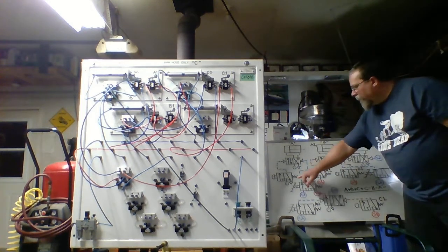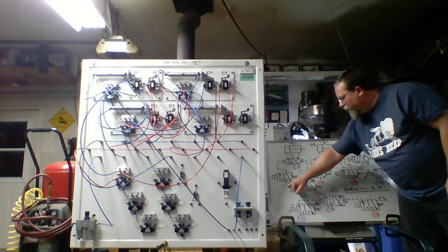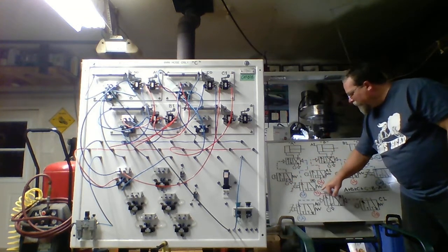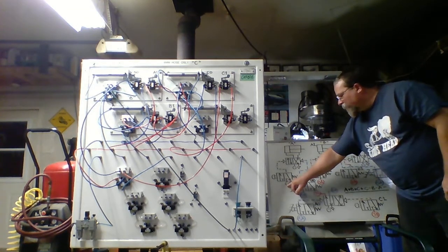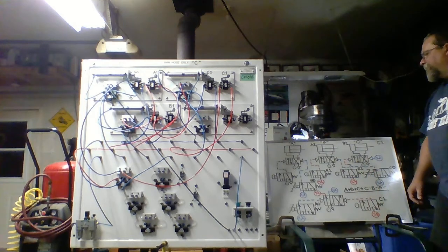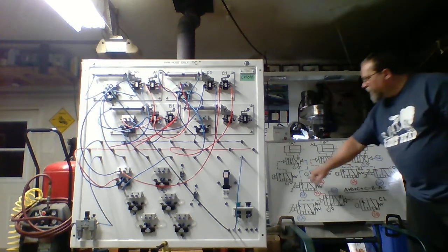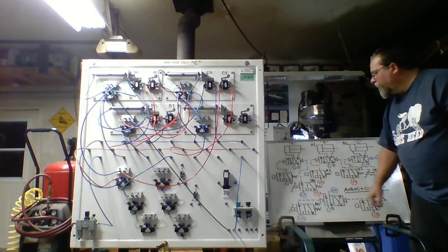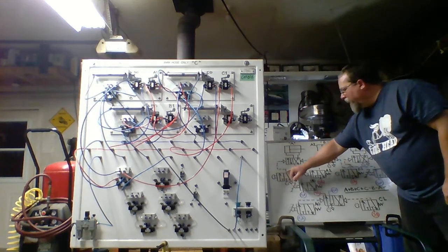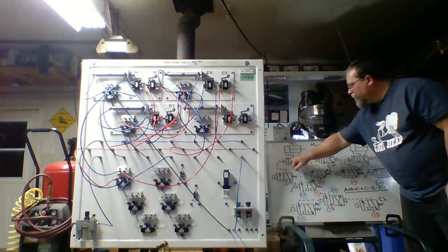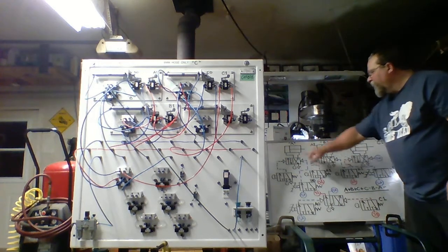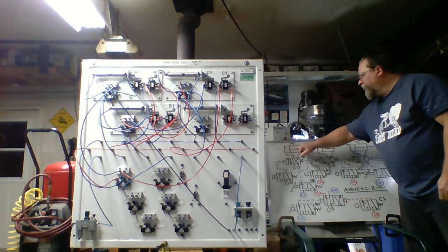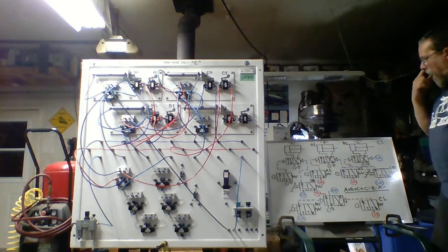Looking over here, our start button, I've supplied it with the main source. You can supply it with source 1. With the main source, there's no conflict. It's not going to have any issues. We have a push button, 3 two-way, normally closed, spring return. When I open the flow path here, you can see the pilot signal shifting the 4 two-way, which will charge the blind end for cylinder A and have it extend. So when A extends, it gets on A1.